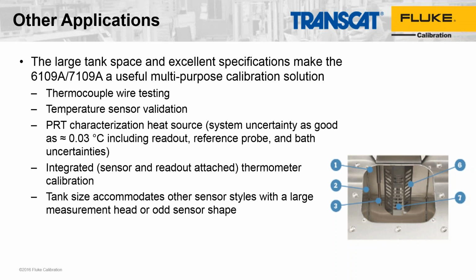We've talked mostly about using the 7109A and 6109A for calibrating sanitary sensors or tri-clamp sensors. But in general, because of the tank size and the good uniformity specs, it's useful for many of the other common calibration applications that are in a cal lab or in a manufacturing and testing environment.